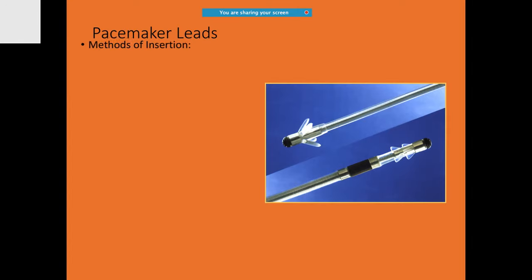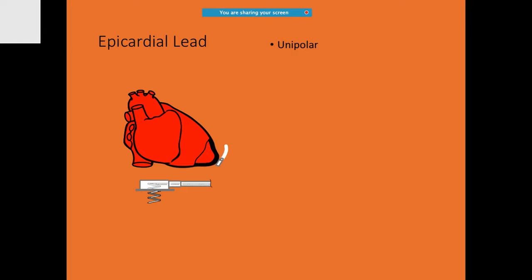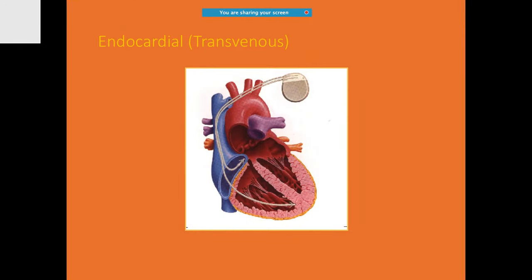There are various types of leads available — either endocardial or epicardial. Epicardial leads are mostly used by surgeons; most of them are unipolar and use higher thresholds. Cardiologists tend to use endocardial leads. Endocardial leads, on the basis of their morphology especially at the tip, may need passive fixation — for example, the tined tip or the finned tip allows passive fixation.